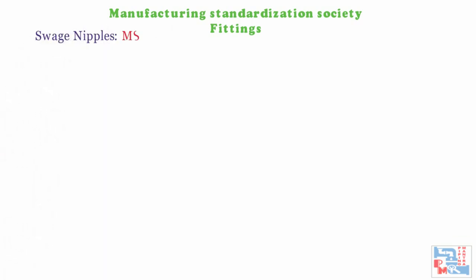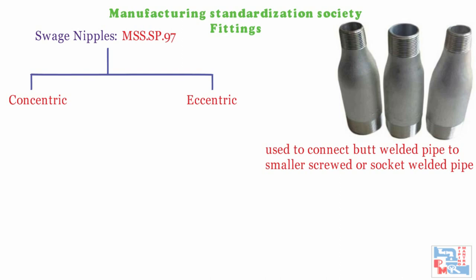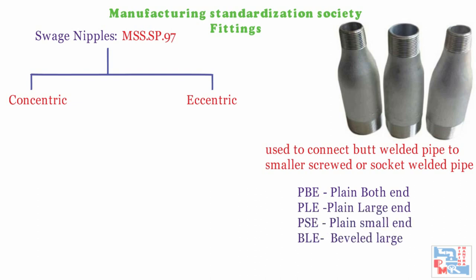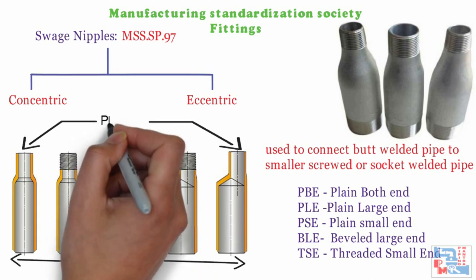Let's talk about special fittings by MSS — Manufacturing Standardization Society. First are swage nipples per MSS SP97. Swage nipples are like reducers but are used to connect butt welded pipe to smaller threaded or socket welded pipe. Like reducers, swage nipples are available in eccentric and concentric types. Various combinations of end connections are possible — PBE (plain both ends), PLE (plain large end), PSE (plain small end), BLE (beveled large end), TSE (threaded small end). Most conveniently, the larger end has a beveled end and the smaller end is plain or threaded.